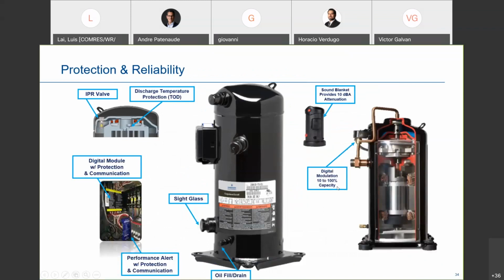If sound is an issue, the Europeans have a sound blanket that you can use for fixed capacity, and there's digital ones as well. These models have internal pressure relief valves, so if the differential in discharge to suction exceeds X amount of pressure, that internal pressure relief valve will open and allow the pressure to be relieved internal to the shell and on top of the motor overload to turn the compressor off as a protection.